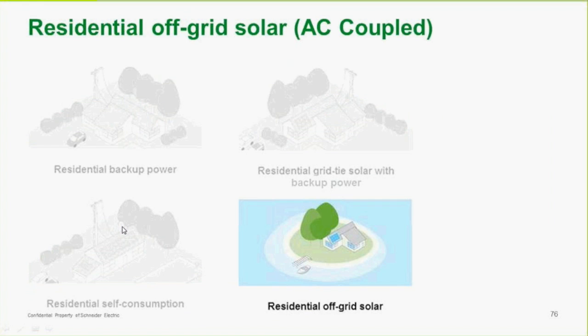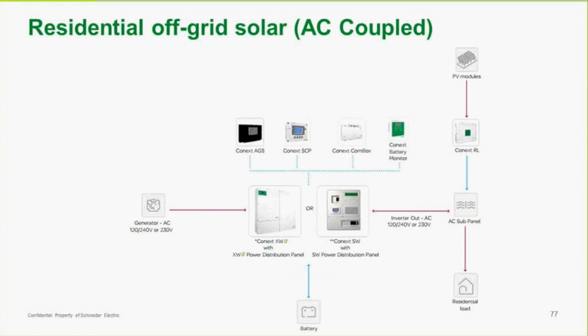And we have residential off-grid solar. So now we're completely off the grid. In this case, we have an AC coupled system that's connected to the XW Plus. Both the outputs of the inverter and the grid-tied inverter are tied to the AC bus in the sub-panel. Once the battery's charged up, the XW Plus is in charge of how much power is coming from the grid-tied inverter. And if the battery gets run down, then we have a generator that will start up and keep things going.